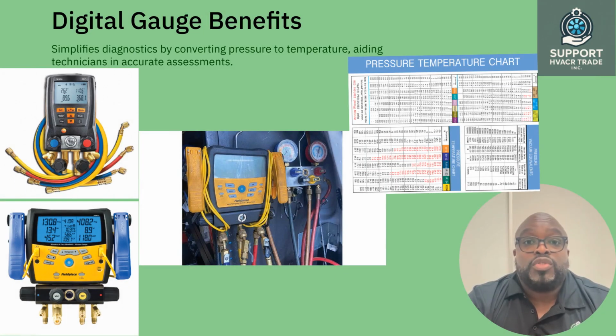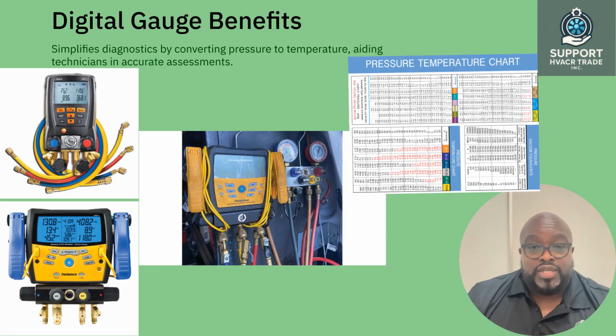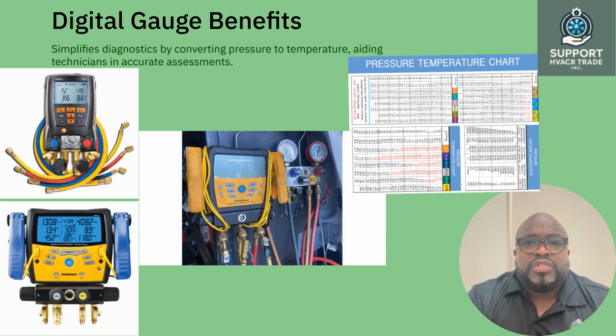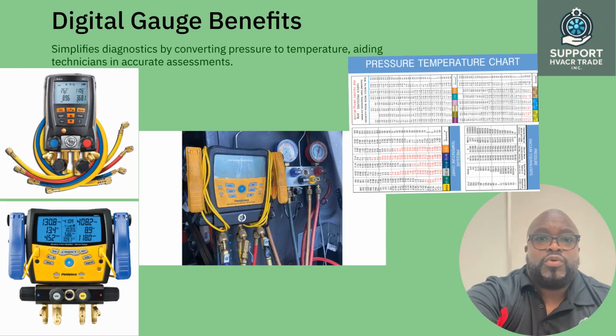In the world of HVAC, tools are everything. And one tool that's changing the game is the digital manifold gauge set. Let's break it down so you can see why it makes diagnostics easier, faster, and more accurate. Unlike analog gauges, digital sets do the hard work for you. They automatically convert pressure into temperature so you don't have to flip through a PT chart. The display shows low side and high side pressure, saturated temperature, and in many cases, superheat and subcooling calculations right on the screen. At first, the buttons might seem intimidating, but with a little practice, you'll quickly learn how to change refrigerant type, switch between Fahrenheit and Celsius, and even record your readings.